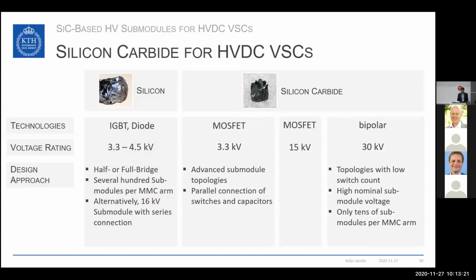For silicon carbide devices, different approaches are proposed in this thesis. One would be to use silicon carbide MOSFETs, as they are already available today, maybe with a bit higher power rating. Those have a voltage rating of 3.3 kilovolts. We would use advanced submodule topologies for these, and these topologies use the parallel connection of switches and capacitors. A totally different approach is the use of silicon carbide bipolar devices. Those can have higher blocking voltages, for example, 30 kV. And here we would use a topology with a low switch count. This enables us to have submodules with a high nominal submodule voltage, and then we would only use several tens of submodules per MMC arm. If we use MOSFETs with high blocking voltage, we could have an approach that is somewhere between these two.